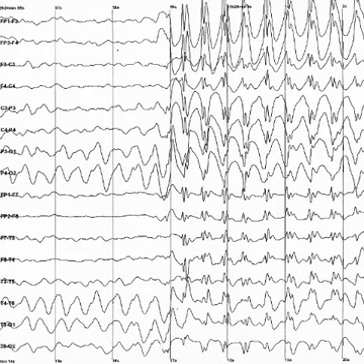In conventional scalp EEG, the recording is obtained by placing electrodes on the scalp with a conductive gel or paste, usually after preparing the scalp area by light abrasion to reduce impedance due to dead skin cells. Many systems typically use electrodes, each of which is attached to an individual wire. Some systems use caps or nets into which electrodes are embedded, this is particularly common when high density arrays of electrodes are needed. Electrode locations and names are specified by the international 10 to 20 system for most clinical and research applications.